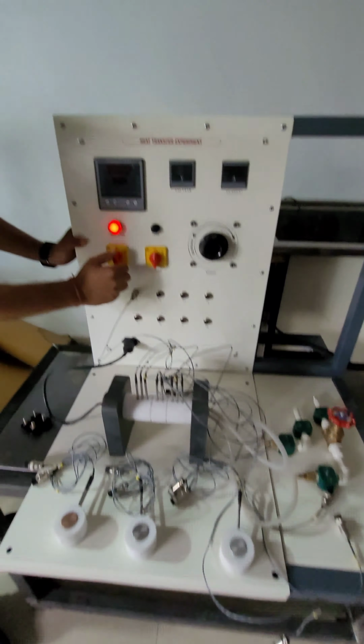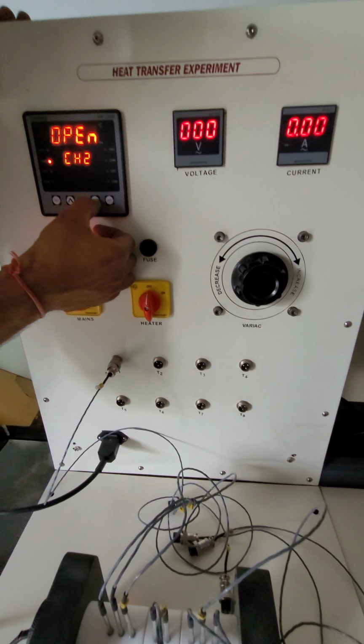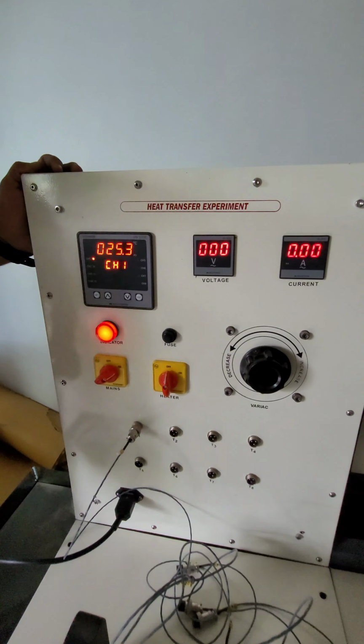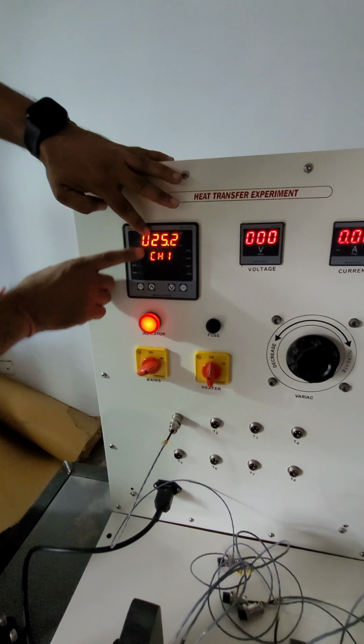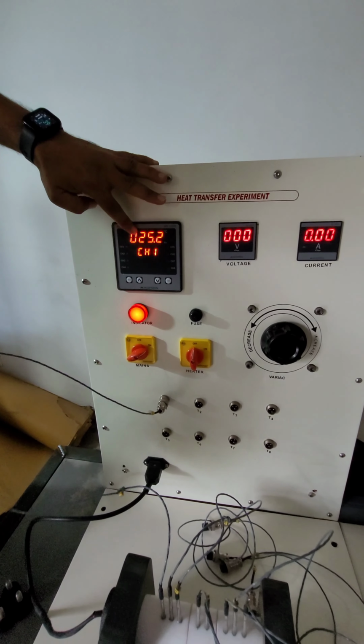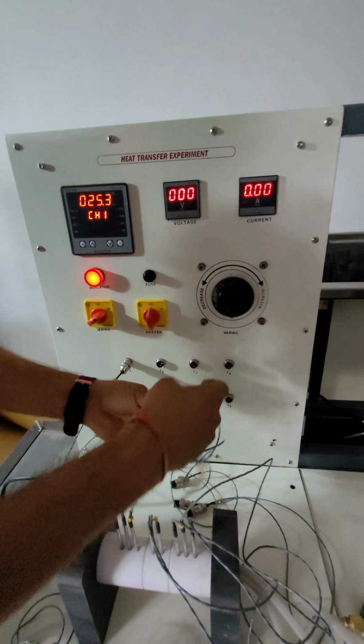As you see, this is the main switch. So this is indicating the temperature. This is showing open because there is nothing connected to this connector. So when I go to the first temperature sensor, you can see that it is showing the temperature at the first point, 25.2.